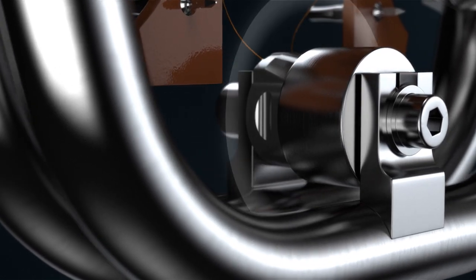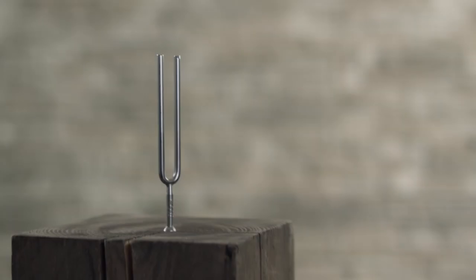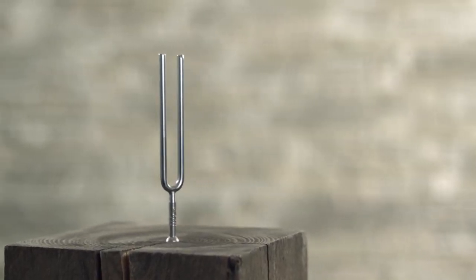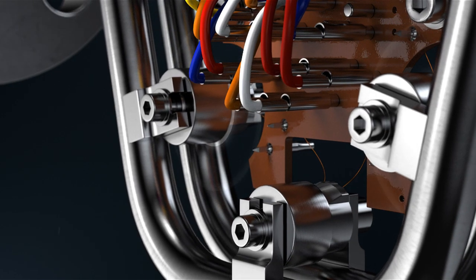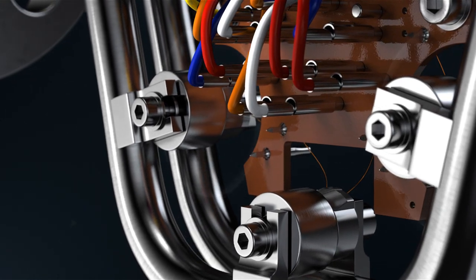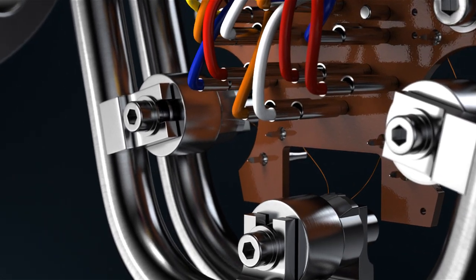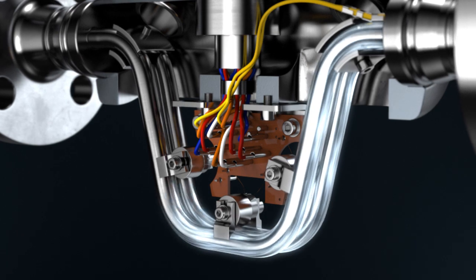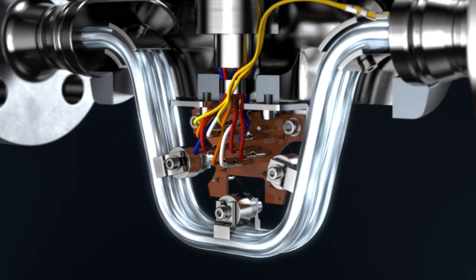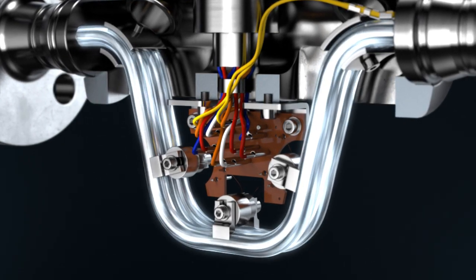The tubes oscillate with a resonance frequency, similarly to a tuning fork. The oscillation is measured precisely by two pickups at the inlet and outlet sections. If liquids or gases now flow through the tubes, a phase shift occurs, as with a water hose.